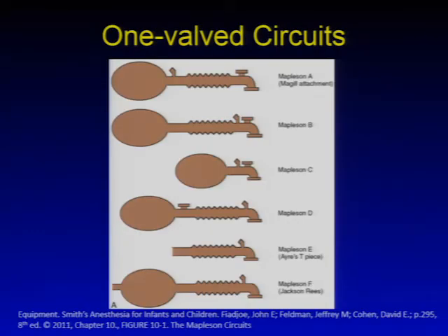Valve circuits developed out of the need to control ventilation. Closing an adjustable valve on these Mapleson circuits allows the addition of positive pressure ventilation as well as PEEP. Mapleson systems are classified based on the location of the fresh gas inflow and overflow valves relative to the patient connection. They all share the benefit of decreased resistance due to the absence of unidirectional valves and canisters, such as in our circle systems or current modern anesthesia machines. Unfortunately, rebreathing and the resulting hypercarbia and respiratory acidosis can become a problem. On the other hand, rebreathing does conserve humidity, heat, and anesthetic gases.